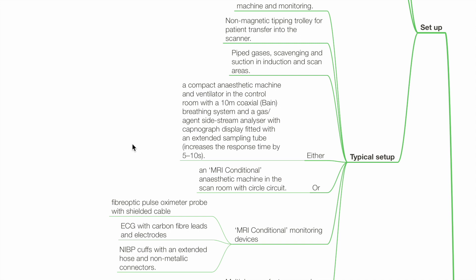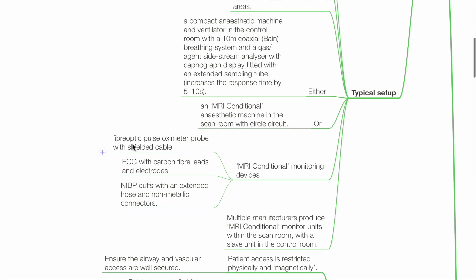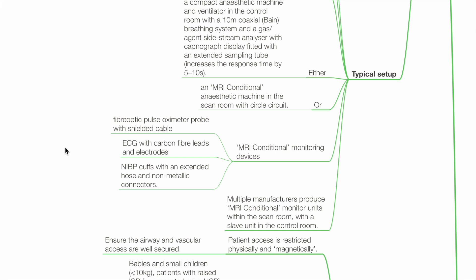The response time is increased by 5 to 10 seconds with this setup. Alternatively, use an MRI-conditional anaesthetic machine in the scan room with a circle circuit. MRI-conditional monitoring devices include a fibre optic pulse oximeter probe with shielded cable, ECG with carbon fibre leads and electrodes, and NIBP cuffs with an extended hose and non-metallic connectors.